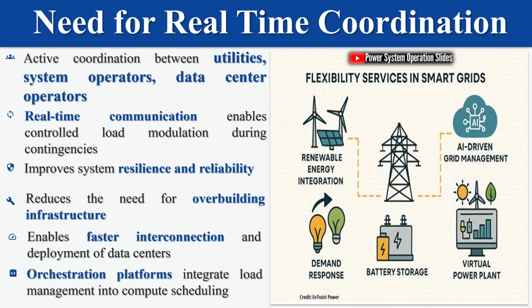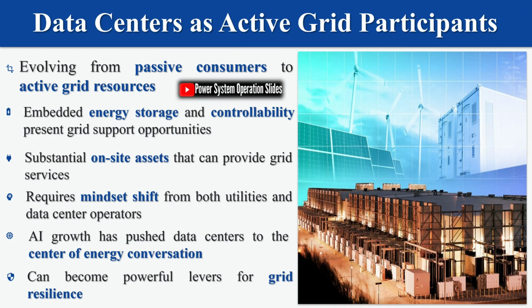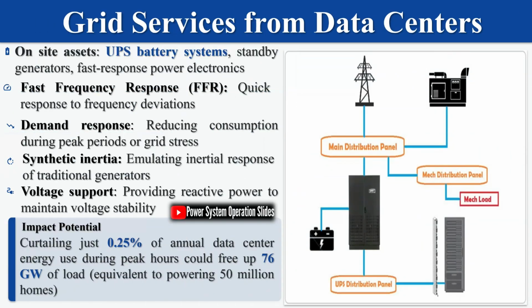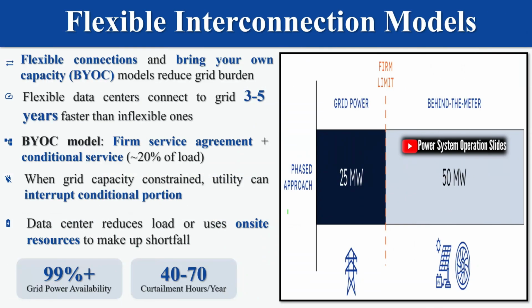They can also participate in demand response programs, reducing consumption during peak periods or grid stress. Through their power electronics, data centers can provide synthetic inertia, emulating the inertial response of traditional generators, and offer voltage support by providing reactive power to maintain voltage stability. By temporarily reducing load or islanding from the grid during contingencies, data centers can actively contribute to system stability. Flexible interconnection models are emerging as a key enabler for this transformation.